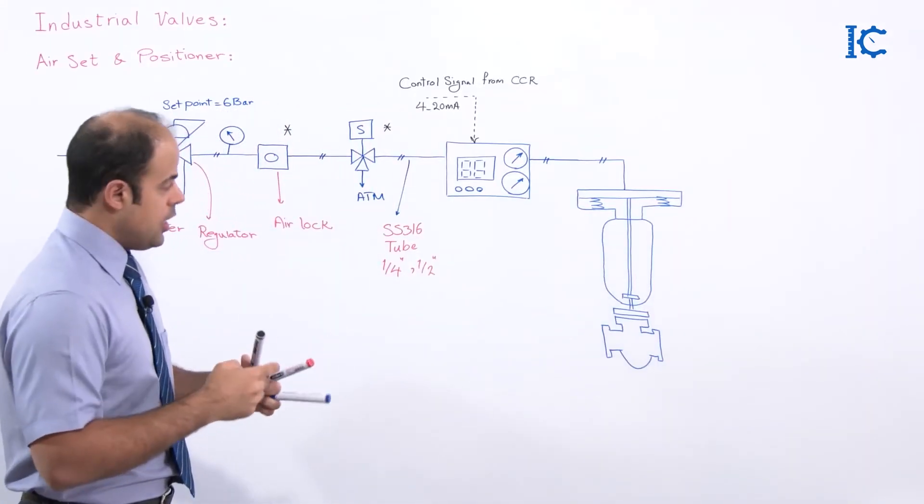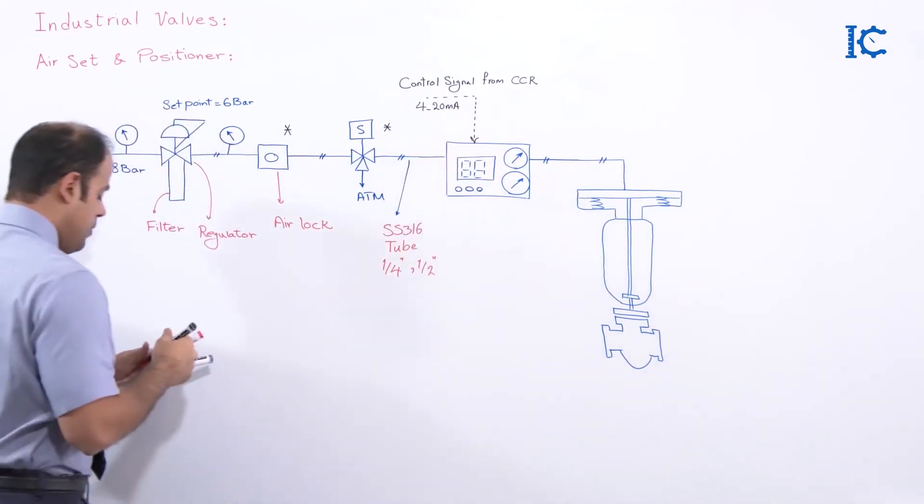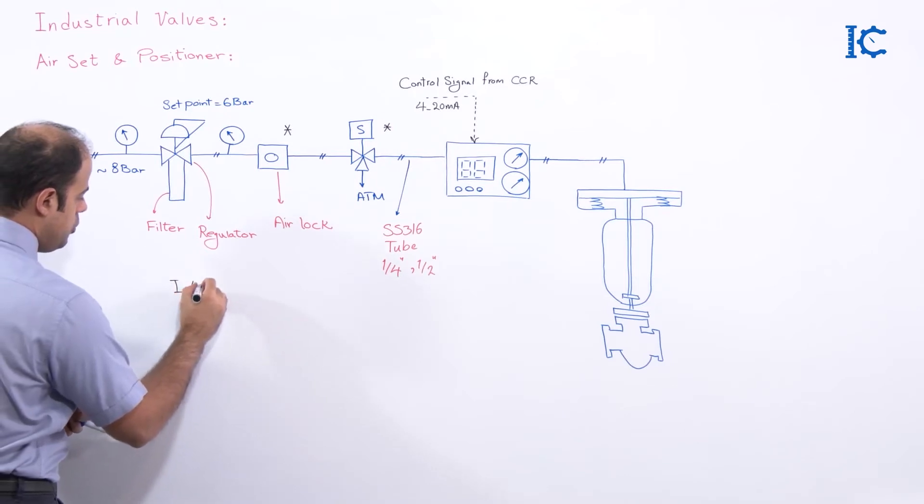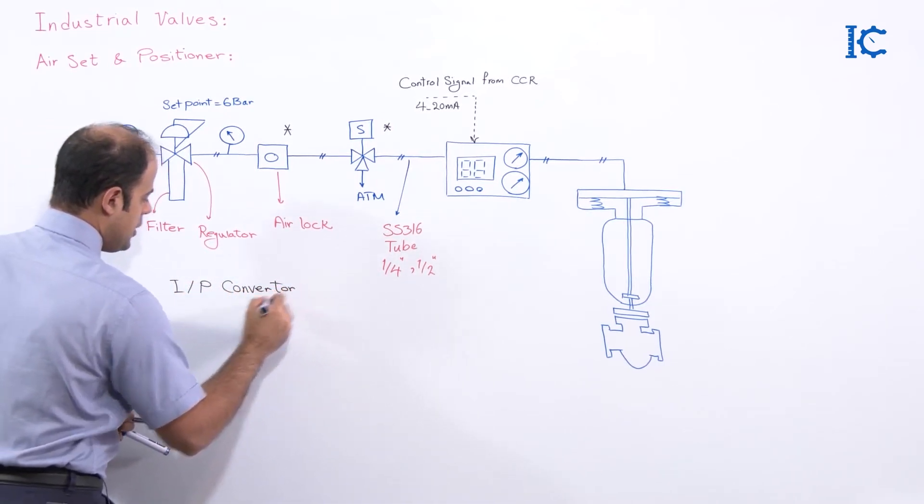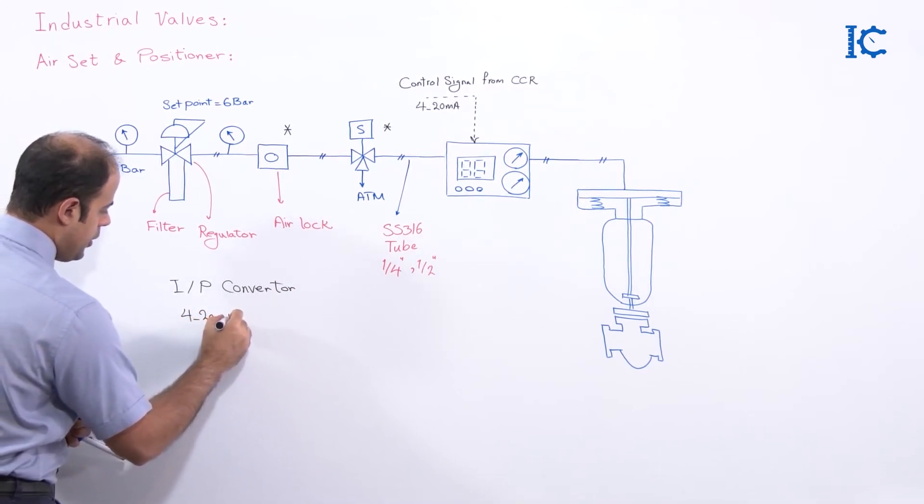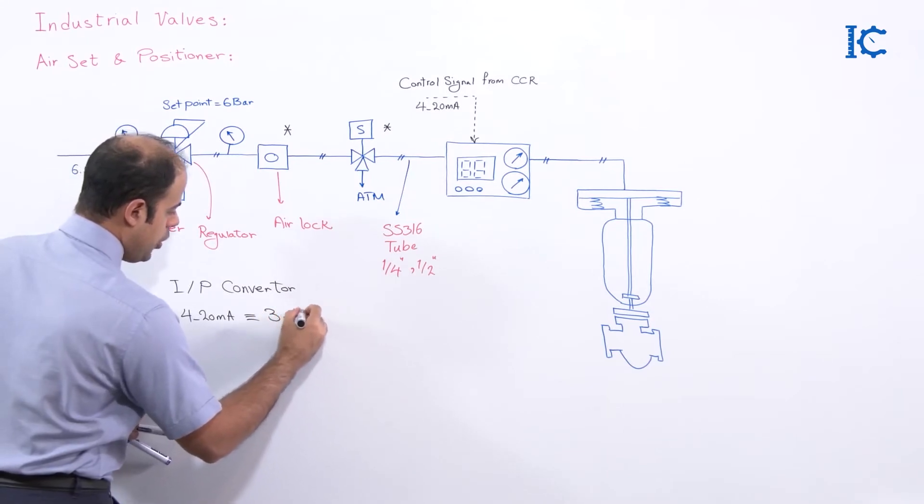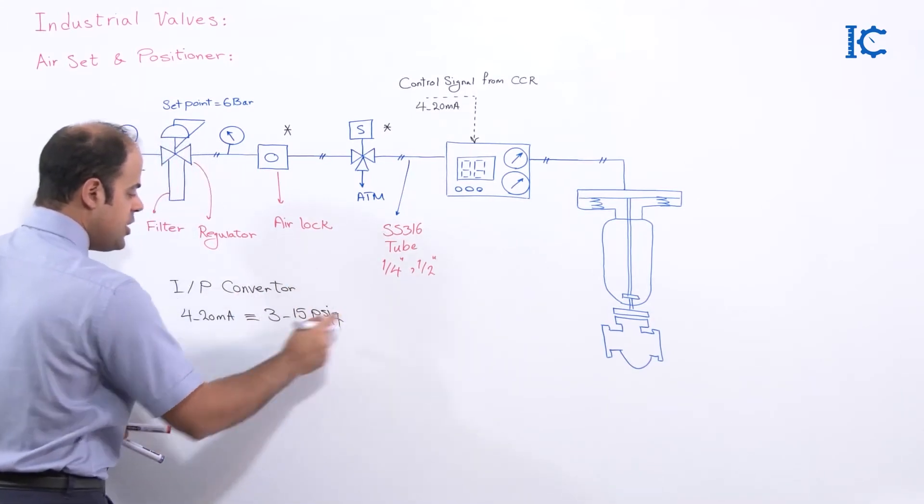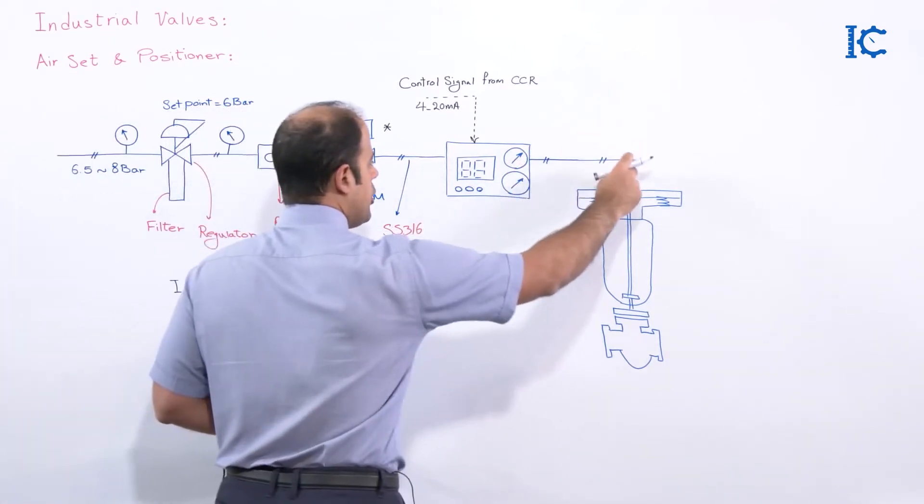So as you could remember, there is a unit in the positioner which is called an I2P converter. It means that 4-20 mA is going to be changed to 3-15 psig, and with the help of this air control signal we can have some pressure here too.